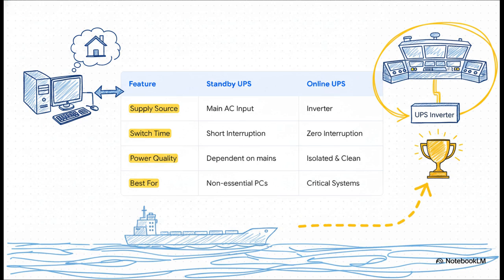It's just too long. That's why they use what's called an online UPS. With an online UPS, the critical equipment is always running off the UPS's power. That means there is zero interruption. Zero. It's the undisputed gold standard for these systems.